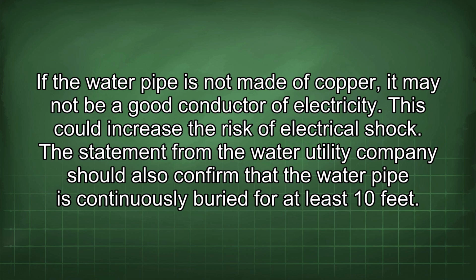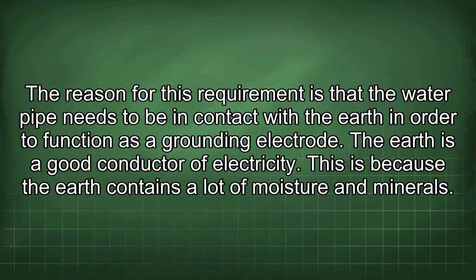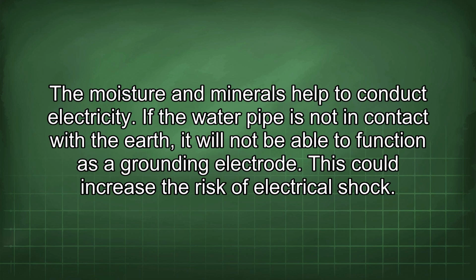The statement from the water utility company should also confirm that the water pipe is continuously buried for at least 10 feet. The reason for this requirement is that the water pipe needs to be in contact with the earth in order to function as a grounding electrode. The earth is a good conductor of electricity. This is because the earth contains a lot of moisture and minerals. The moisture and minerals help to conduct electricity. If the water pipe is not in contact with the earth, it will not be able to function as a grounding electrode. This could increase the risk of electrical shock.